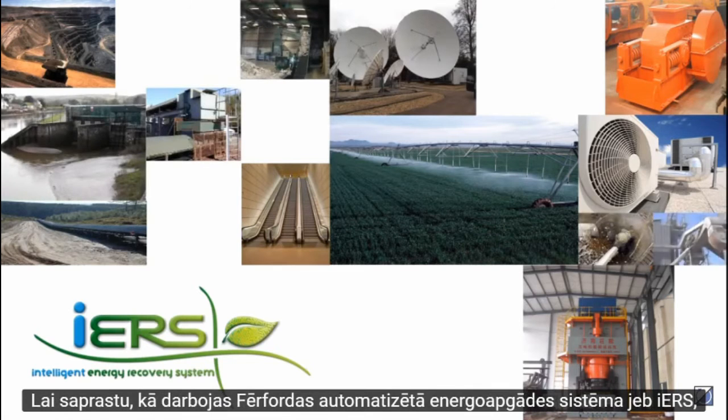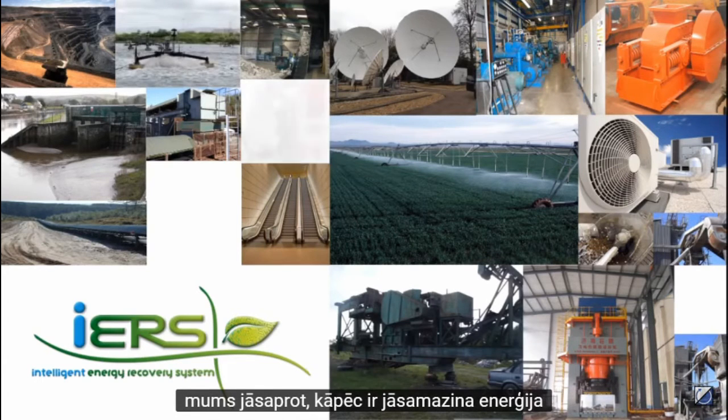To understand how Fairford's Intelligent Energy Recovery System, or iERS, works, we need to understand why there is a need to reduce the energy consumption of AC induction motors. When a motor is fully loaded, it's designed to be as energy efficient as possible and will work at the design power factor.